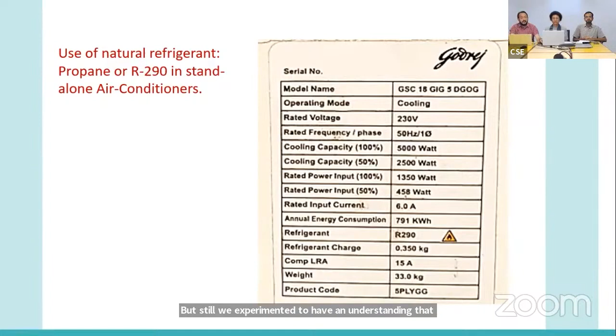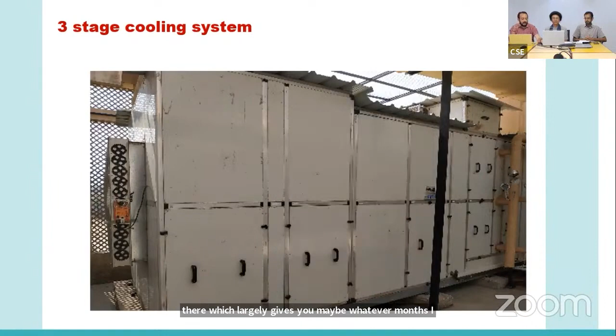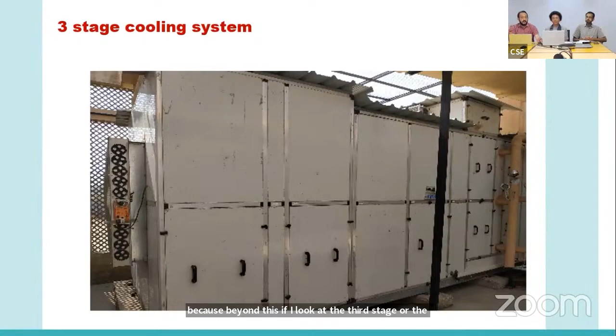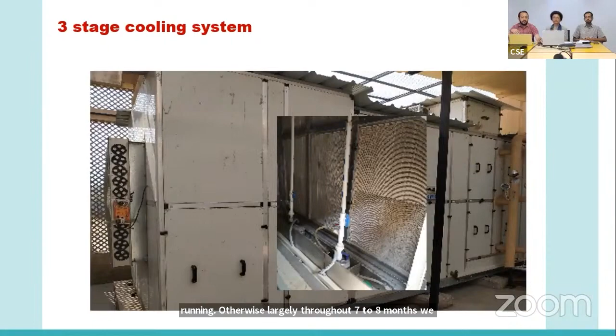We have a 3-stage cooling system, which Professor Mathur was explaining. I can show you how the air handling unit works, running on direct and indirect cooling. Here are the evaporative pads, and stored water, which gives us the months where we're not using air conditioning. The 3rd stage or last pocket of cabinets is for the chillers or cold pipe. Otherwise, throughout 7 to 8 months we run with these direct or indirect systems, with other possibilities available too.